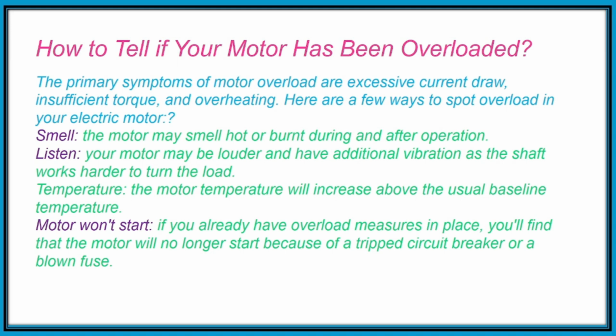Smell. The motor may smell hot or burnt during or after operation. Listen. Your motor may be louder and have additional vibration as the shaft works harder against the load. Temperature. The motor temperature will increase above the usual baseline temperature. Motor won't start. If you already have overload measures in place, you'll find that your motor will no longer start because of a tripped circuit breaker or a blown fuse.